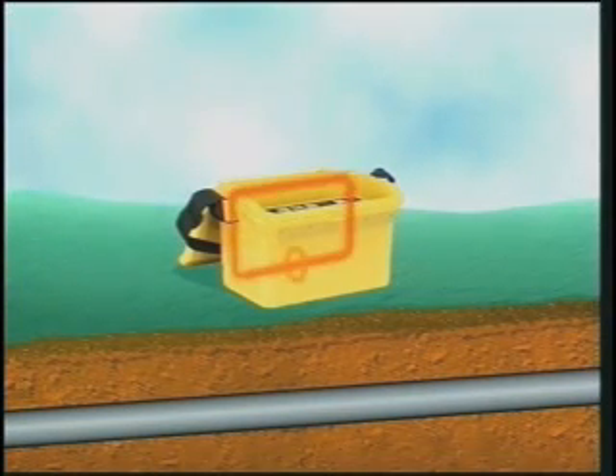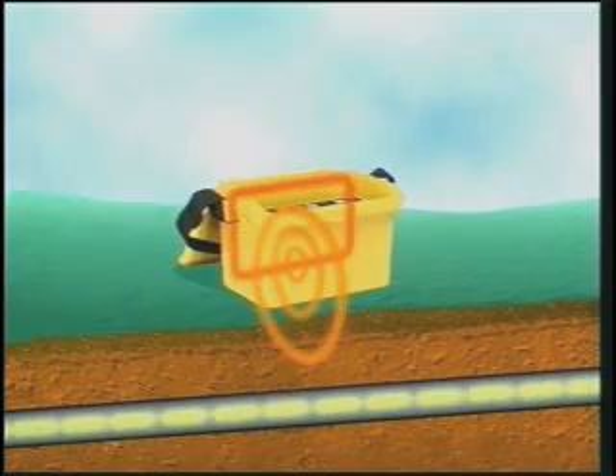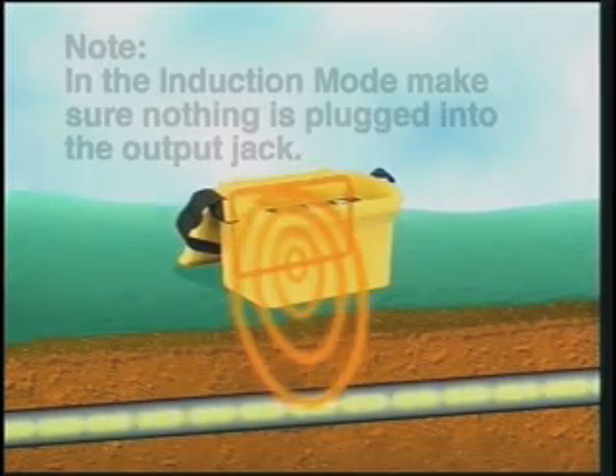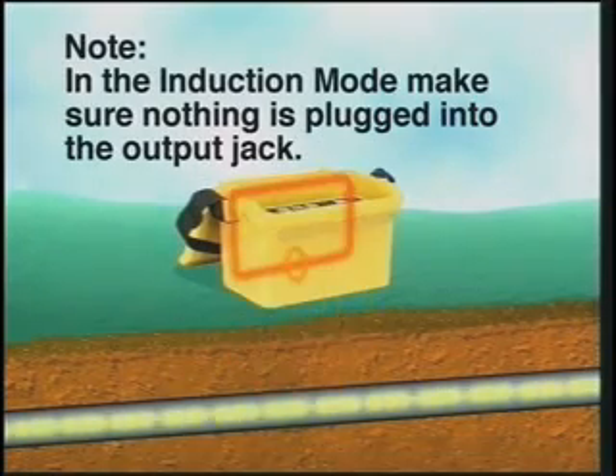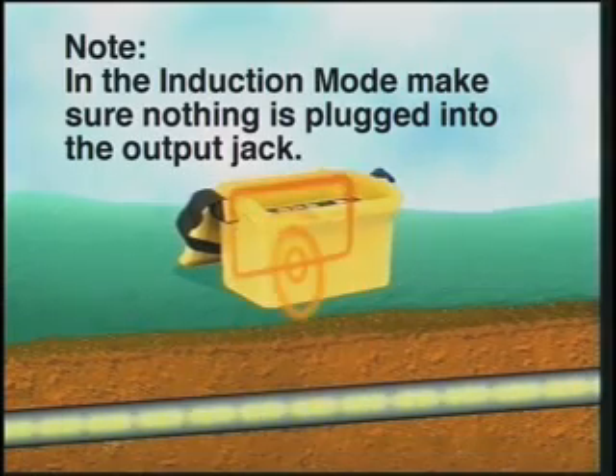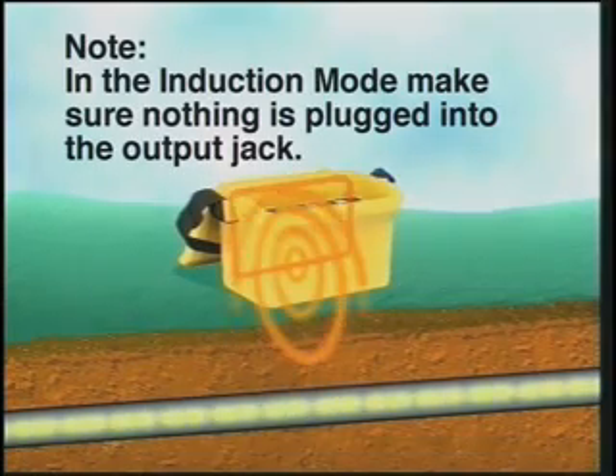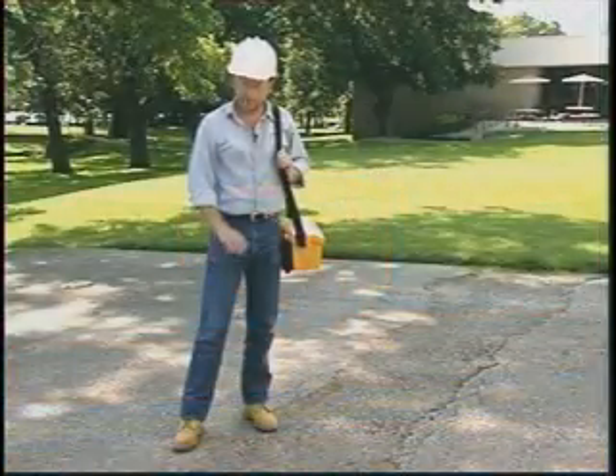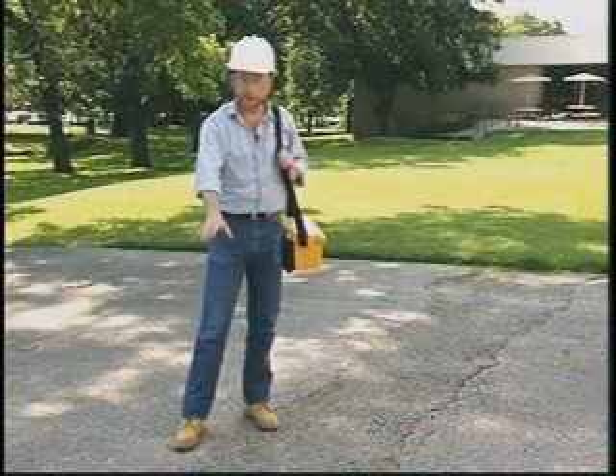When surface access to a buried conductor is not available, you can still apply a signal to the conductor using the induction method. The transmitter signal comes from an internal antenna and couples onto the buried conductor. This is a good example of when to use the induction method.